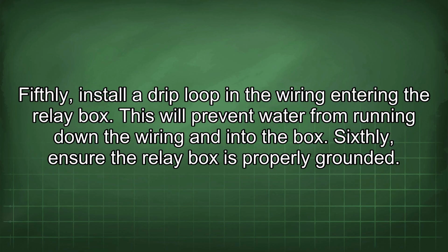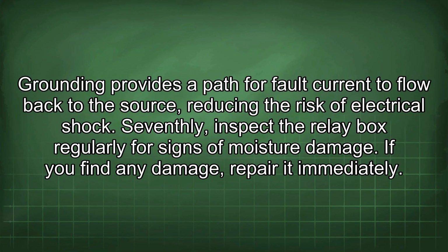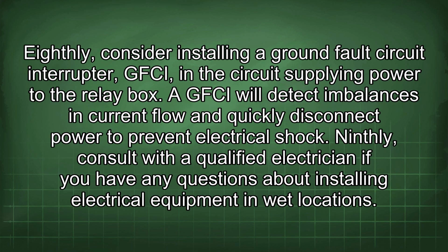Fifthly, install a drip loop in the wiring entering the relay box. This will prevent water from running down the wiring and into the box. Sixthly, ensure the relay box is properly grounded. Grounding provides a path for fault current to flow back to the source, reducing the risk of electrical shock. Seventhly, inspect the relay box regularly for signs of moisture damage. If you find any damage, repair it immediately. Eighthly, consider installing a ground fault circuit interrupter (GFCI) in the circuit supplying power to the relay box. A GFCI will detect imbalances in current flow and quickly disconnect power to prevent electrical shock.